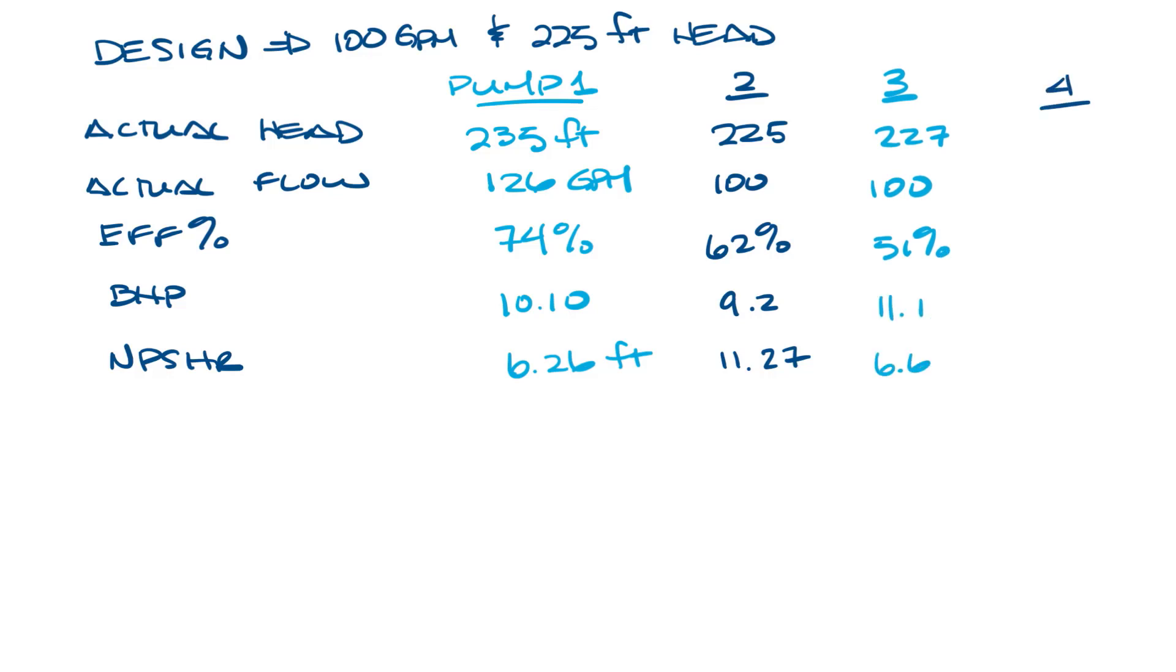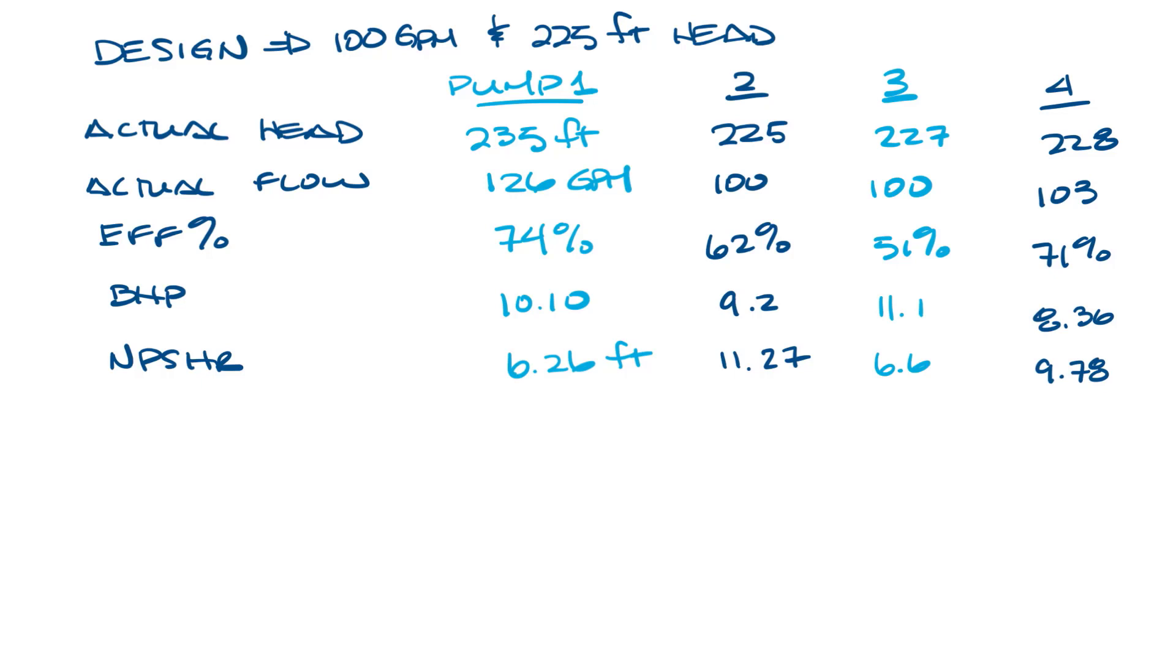And then the fourth one would be 228 feet ahead, 103 GPM, 71%, 8.36 horsepower, and 9.78 feet for NPSHR.